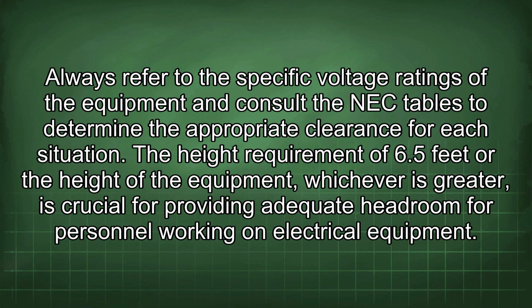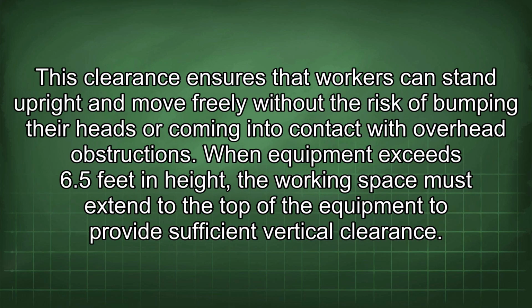Always refer to the specific voltage ratings of the equipment and consult the NEC tables to determine the appropriate clearance for each situation. The height requirement of 6.5 feet or the height of the equipment, whichever is greater, is crucial for providing adequate headroom for personnel working on electrical equipment. This clearance ensures that workers can stand upright and move freely without the risk of bumping their heads or coming into contact with overhead obstructions.